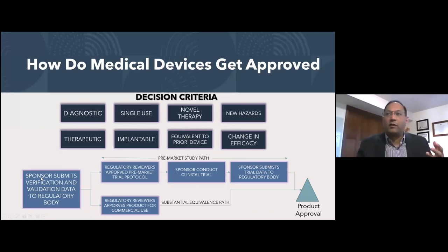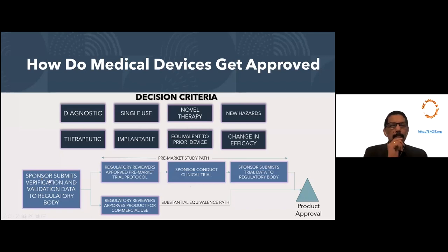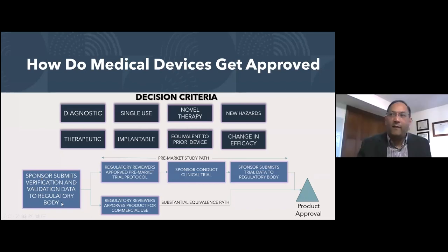The sponsor, meaning an industry player, submits all of the data to a regulatory body and makes an argument that we want to take a substantial equivalent path or the pre-market path. The regulatory agency might come back and say, no, this is not substantial equivalent, you have to go to the pre-market path. If it's a pre-market path, then a protocol is submitted. The protocol is approved. The sponsor conducts the trial.